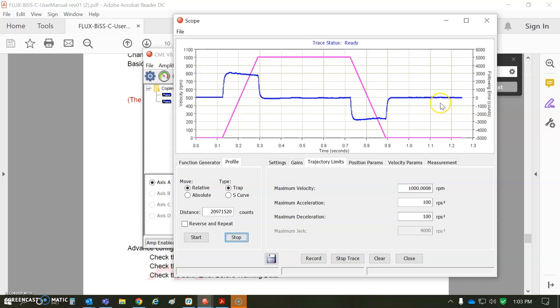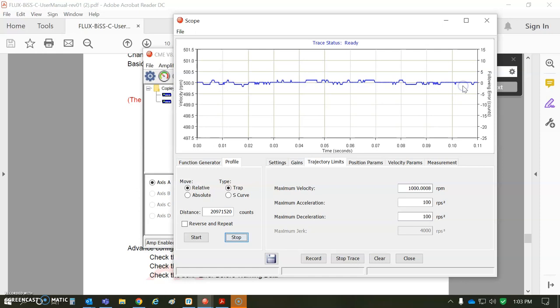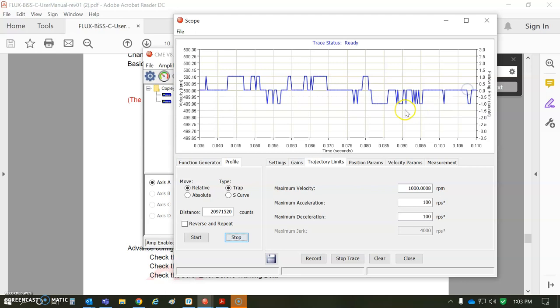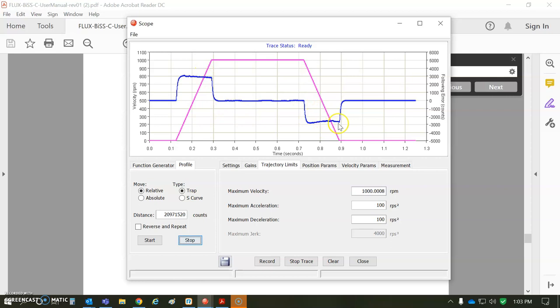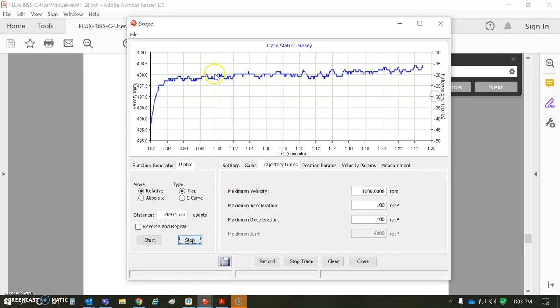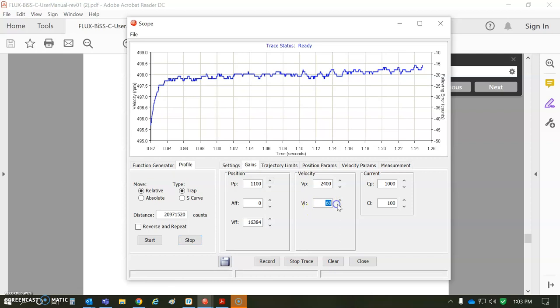If you notice before you're even moving, you get plus or minus a couple of counts here. Looks like a normal quantization of the digital feedback device, plus or minus a count or two. After the move is done, a little bit of error while you're accelerating, a little bit of error while you're decelerating. Not so bad while you're running—a little bit of ripple in there, probably a little torque detent but not very big. Then plus or minus a few counts based on your tuning.